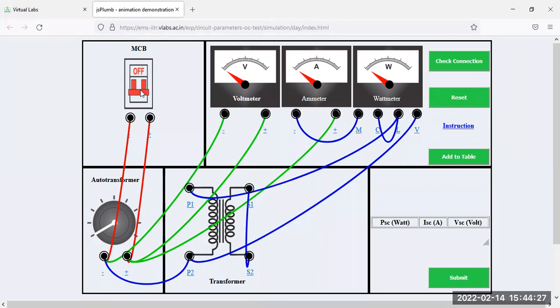Just click on this MCB. So the power supply is on. Okay. And if you click on this button, that means the auto transformer, it is moving the handle of the auto transformer. So yeah, supply is going. So this current is your rated current, and the voltage required during this test is indicated by this voltmeter, and whatever power is consumed during the short circuit test will be indicated by this wattmeter. Okay. So during the short circuit test, we just consider the ohmic losses and neglect the core losses.